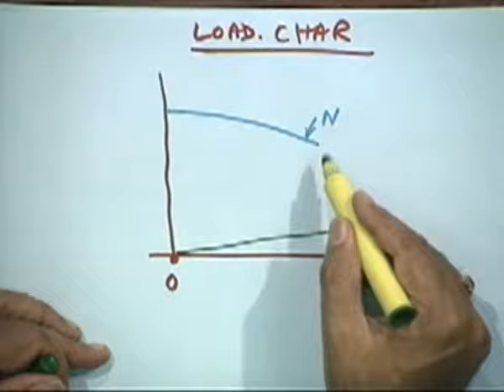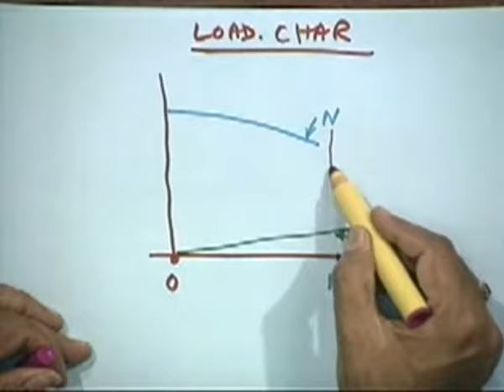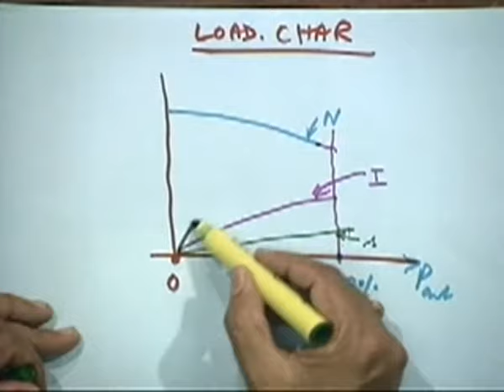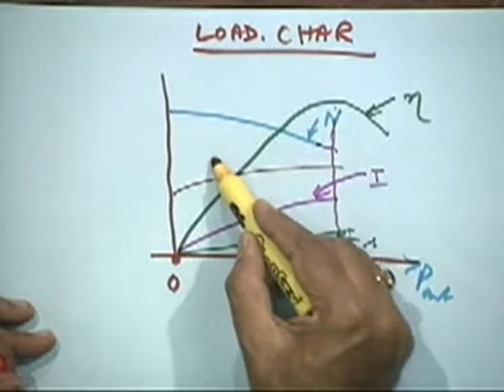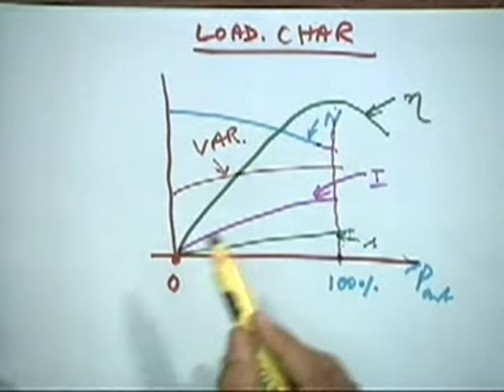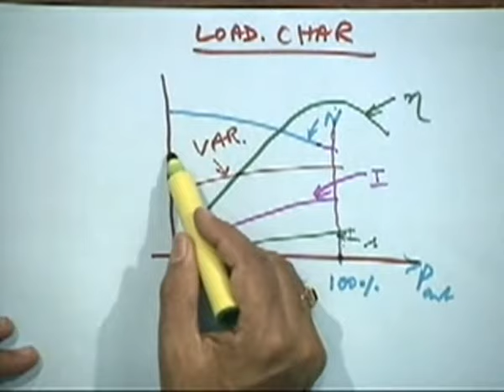because speed drop means slip would increase, and you would expect the current to go up, because at 100%, this is a full load condition, you know the current would go up, right, and your efficiency may also follow certain figures. This may be efficiency, right, and then there will be some reactive power and some variation of maybe some power factor. Power factor may be poor at low load, maybe, and it will be improved power factor. So, all these quantities you can plot, right.